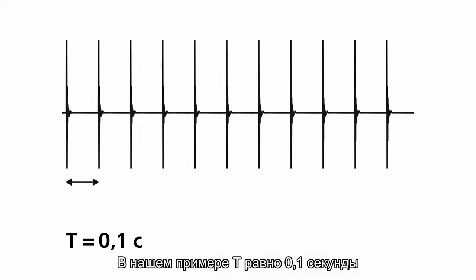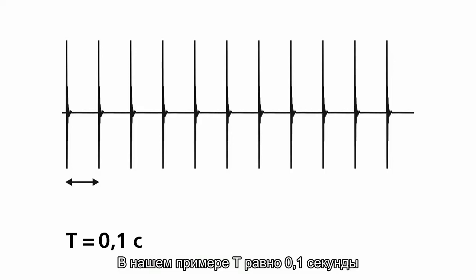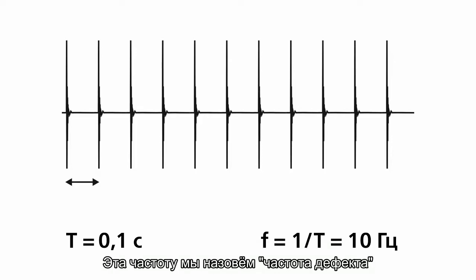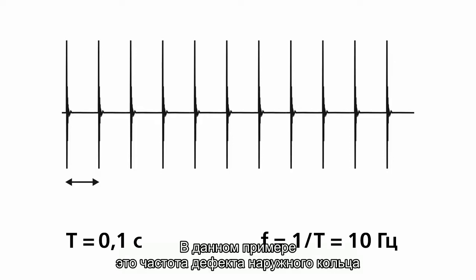In our example t is equal to 0.1 second. The value equal to 1 divided by t is the repeating frequency of shocks. This frequency we label as fault frequency. In this example it is the outer race fault frequency.